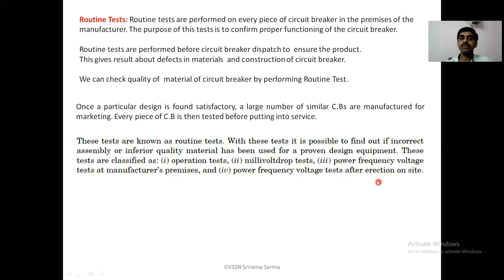Once a particular design is found satisfactory, a large number of similar circuit breakers are manufactured for marketing. So that is the purpose of the routine test. Every piece of circuit breaker is tested before putting into service. Whereas in the type test, every piece is not required to be tested, in the routine test every piece needs to be tested. With this test, it is possible to find out whether incorrect assembly or inferior quality material has been used for a proven design equipment. These tests are classified as operation tests, millivolt drop test, power frequency voltage test at manufacturing premises, and power frequency voltage tests after erection on site.